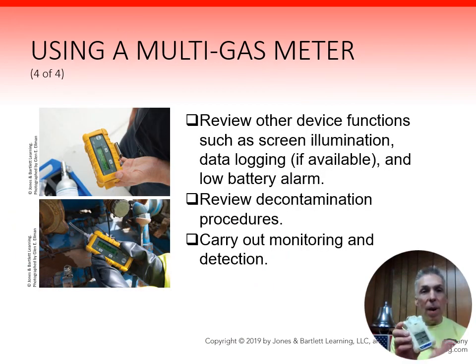Now, once again, with that meter, you want to make sure that that screen illuminates, which should happen during that power on self-test. There is data logging that's available. You can connect this to a PC and download all the logs. Right now, we go with analog, the manually handwritten in-house logs of our bump and calibration tests. And you want to make sure that that low battery alarm does work. The only way to really make sure the low battery alarm works is to let it run out. But that low battery alarm will sound if the batteries get down too low.